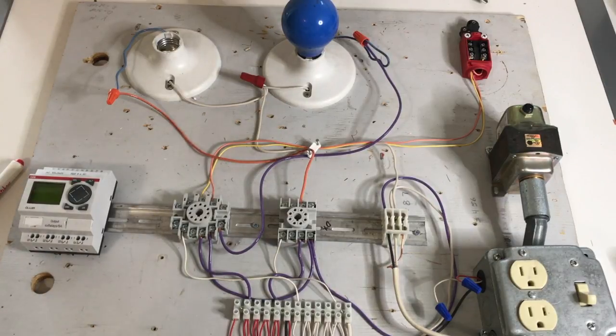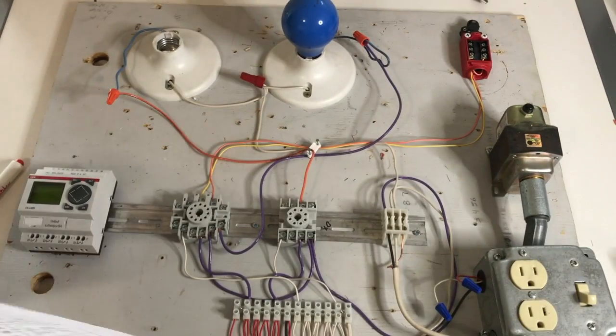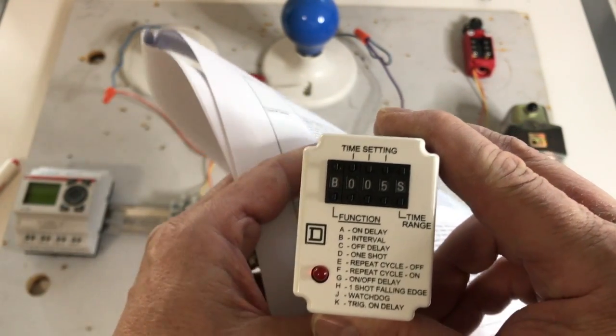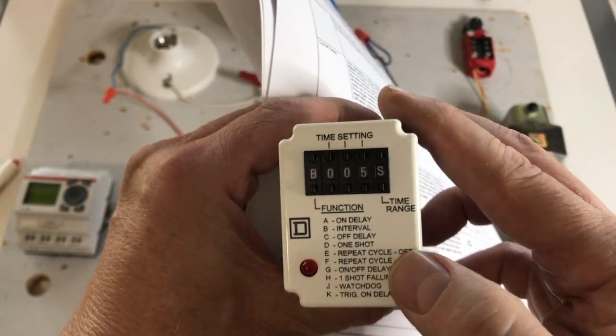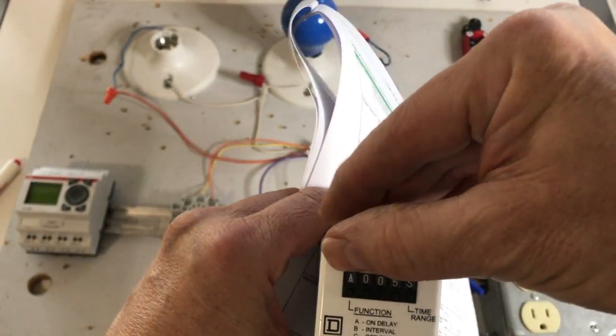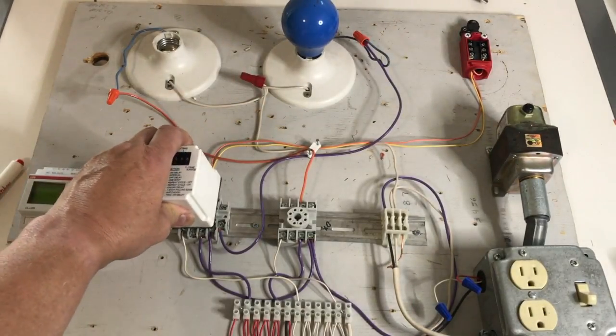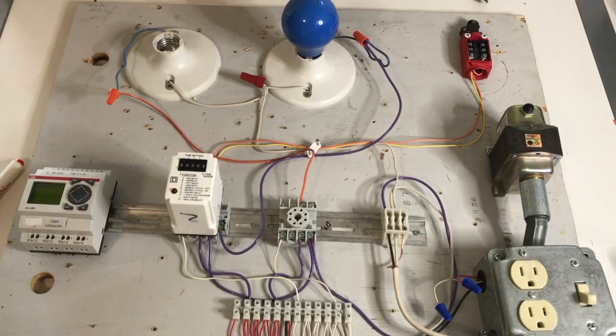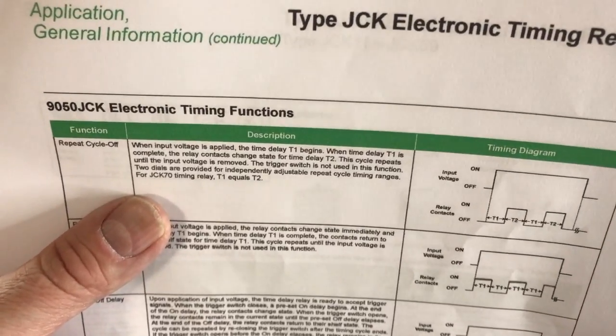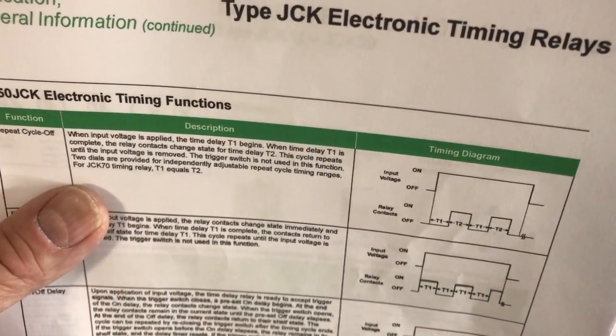What I'm going to talk about next will be our recycle. Let's go back and look at our multifunction relay — they're calling this a repeat cycle. You could do repeat cycle off or repeat cycle on. Let's go ahead with repeat cycle off, so let's change it to E and keep it at 5 seconds. So let's read what a repeat cycle off does: when input voltage is applied, the time delay T1 begins. When time delay T1 is complete, the relay contacts change state. For time delay T2. This cycle repeats until the input voltage is removed.